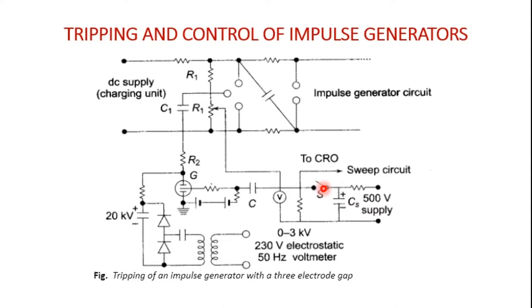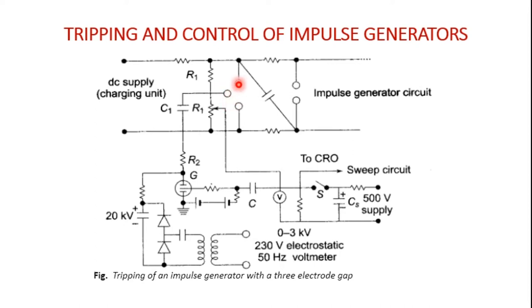When switch S is closed, capacitor C produces an exponentially decaying pulse of positive polarity, which goes to the sweep circuit and initiates an oscilloscope time base. When the thyratron conducts upon receiving the pulse, it produces a negative pulse via capacitance C1 at the central electrode of the three electrode gap arrangement, raising the voltage between the central and top electrode above its sparking potential, initiating conduction and sparking between the two electrodes.